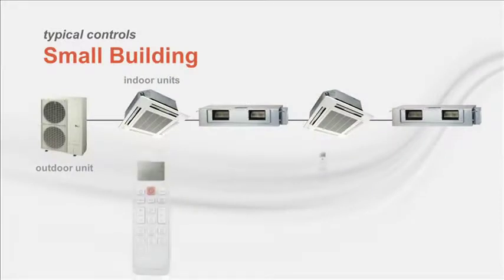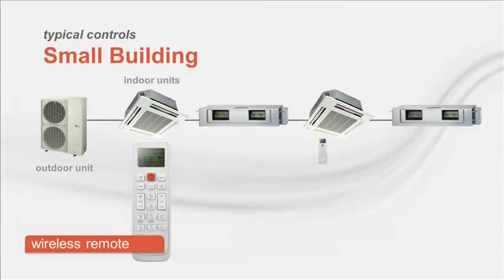Now let's look at the controls that tie the system together. I'll begin with a small building that uses a single VRF system. First, it must be noted that all VRF manufacturers, due to their complex communication requirements, currently use proprietary controls. Most ductless indoor units, like the cassette or high-wall models, utilize a wireless remote control similar to a TV remote. They offer basic capabilities such as on-off, operating mode, fan speed, airflow, and temperature set point. Through multi-channel logic, one wireless remote device can even control multiple indoor units.